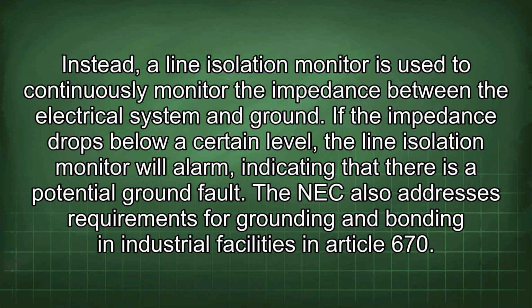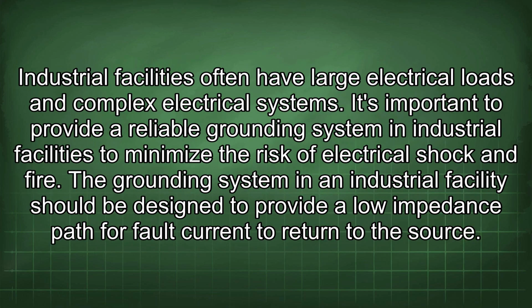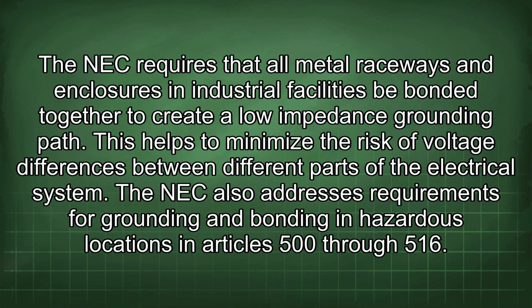The NEC also addresses requirements for grounding and bonding in industrial facilities in Article 670. Industrial facilities often have large electrical loads and complex electrical systems. It's important to provide a reliable grounding system in industrial facilities to minimize the risk of electrical shock and fire. The grounding system in an industrial facility should be designed to provide a low impedance path for fault current to return to the source. The NEC requires that all metal raceways and enclosures in industrial facilities be bonded together to create a low impedance grounding path. This helps to minimize the risk of voltage differences between different parts of the electrical system.